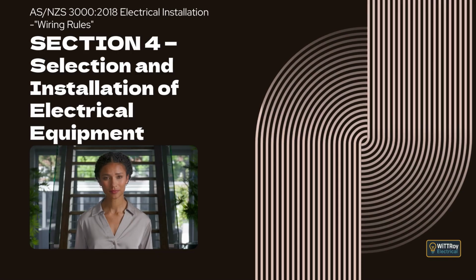Clause 4.2.1 General. This clause explains that electrical equipment must be selected and installed so that, when it is correctly installed and operating as intended, its temperature does not negatively affect the equipment itself, the electrical installation, or anything nearby, whether electrical or not. It explains that ventilation must be provided when needed so operating temperatures stay within the equipment's rated limits when heat is produced in normal use, and it reminds us that temperature can change how equipment performs or behaves, so this must be considered during selection and installation.